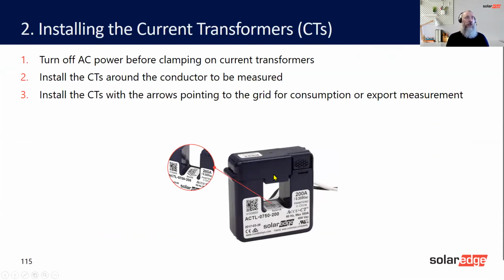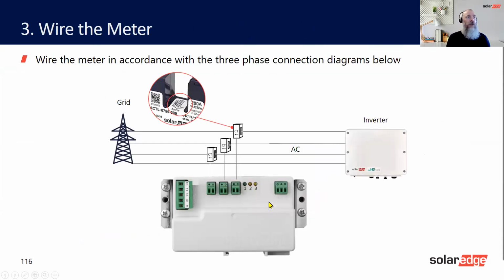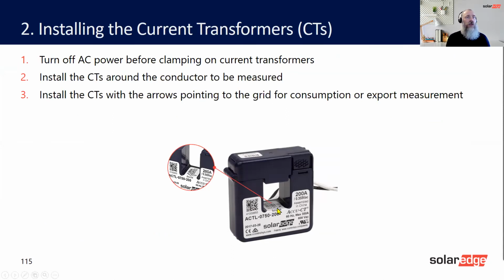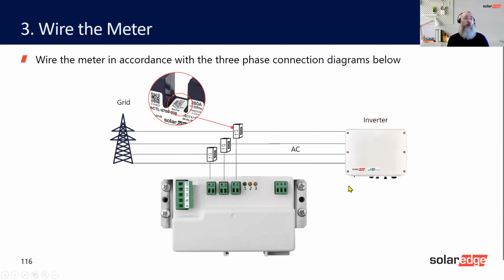Here's your CT, and if you look in here, you can see, whoops, too far, sorry. Let's go back. You can see that the CT has an arrow pointing to source, to grid. Can you see? This is what you need to make sure points to the grid. Again, these are different amperage. This is 200 amp. And most importantly, you must use the SolarEdge CTs, because we run on 0.333 volts as opposed to a ratio. So you must use these ones. If you don't, it won't work, basically.